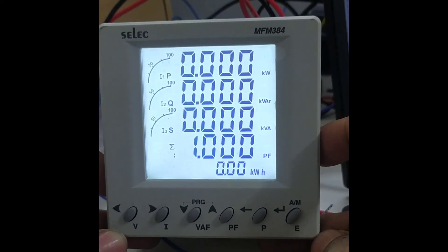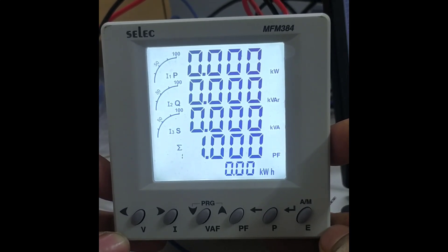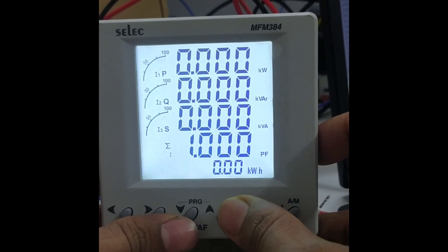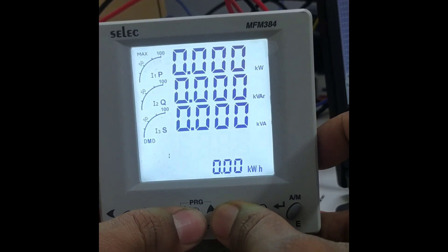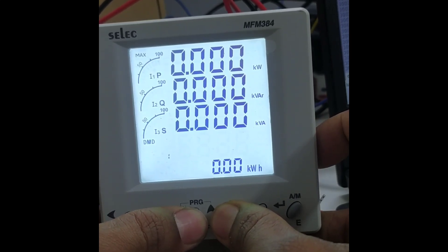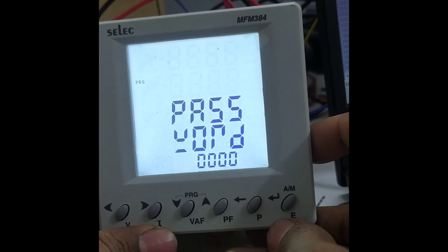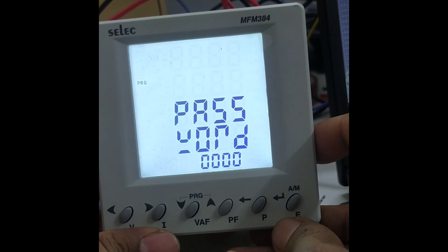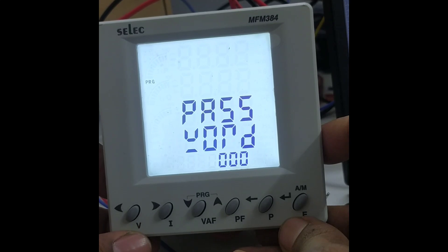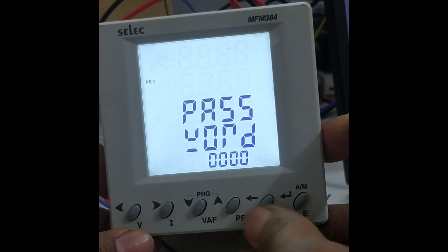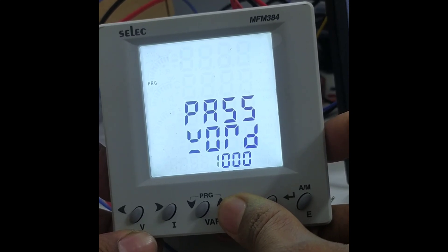In this video we are discussing how to check parameters of the Selec MFM384. Press the upward and downward keys. Now the password screen appears. The default password for these meters is 1000. With the help of the left key, select the digit, and with the help of the upper key, select one and then press enter.